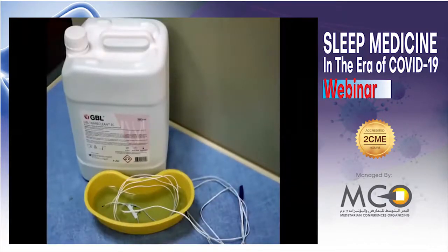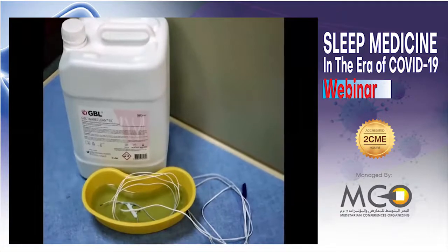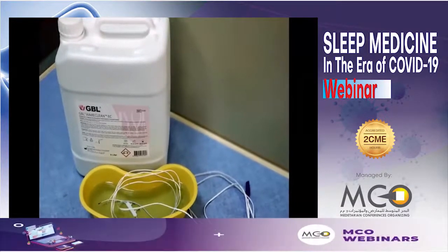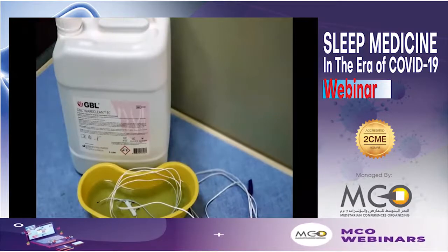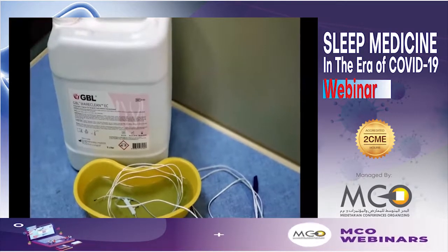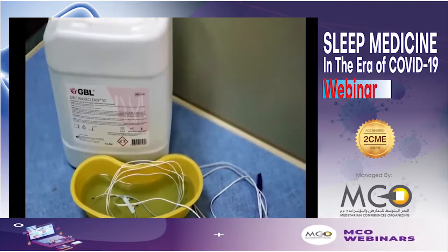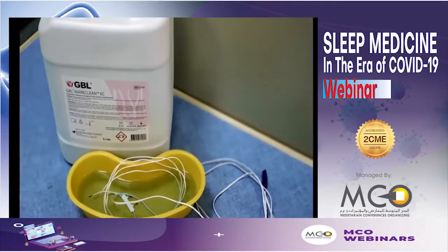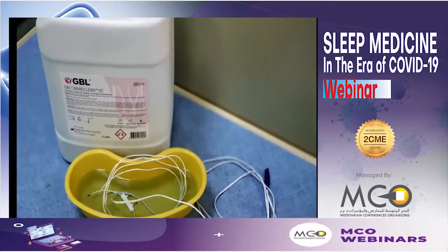Microphone and airflow sensor. Immerse the microphone and thermistor in Cidex and Omnicide solution for 30 minutes. But be careful, do not immerse the other side of the sensors in any solution, as it might damage the head box or the sensor itself.